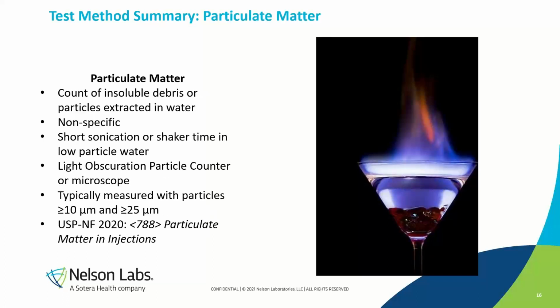Particulate matter. This is the test that again overlaps with gravimetric water. This will give you a count of insoluble debris or particles extracted in water. It's non-specific. It's a shorter sonication or a manual shake or an orbital shake, depending on the specific device, in low particle water. Those particles are going to go into solution pretty easily. We don't have to have an aggressive extraction for this method. We use a light obscuration particle counter, but there is a microscope option available for additional qualitative information. And we typically measure in 2 particle sizes, but other particle sizes are also available. And then the standard we comply with is USP 788, particulate matter for injections.